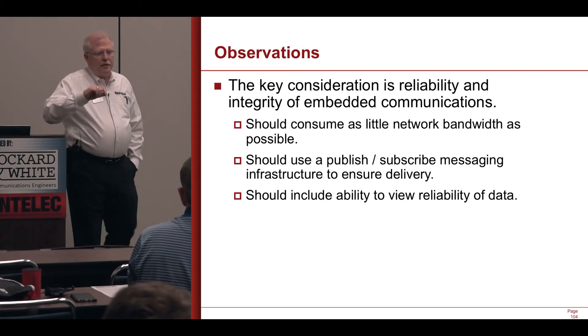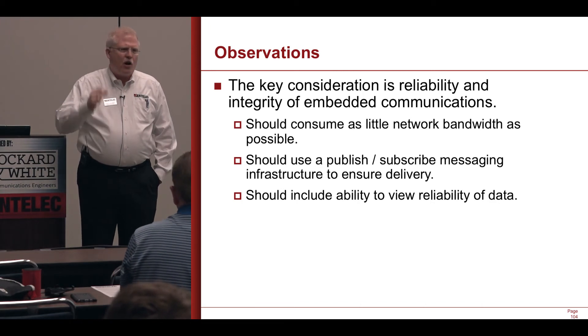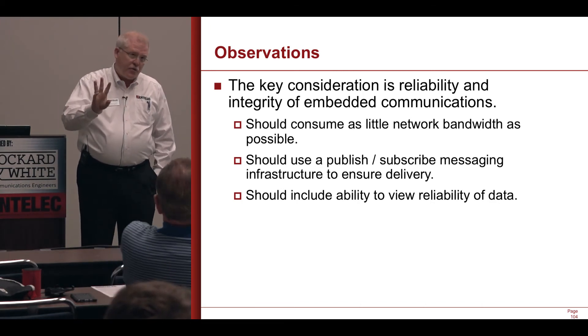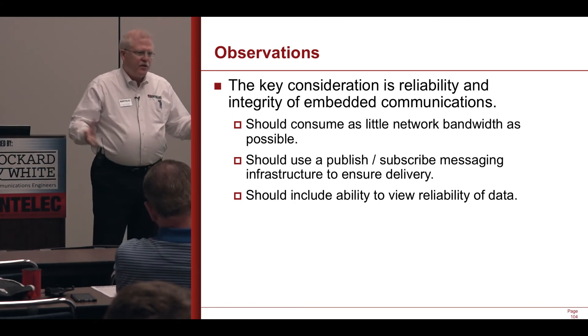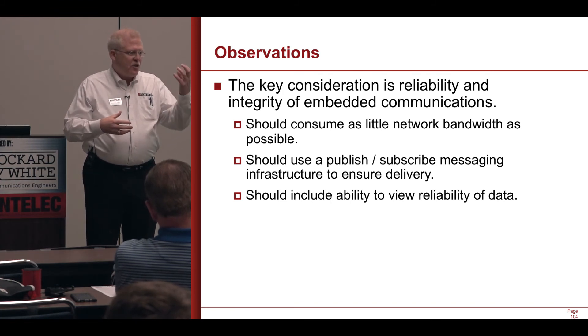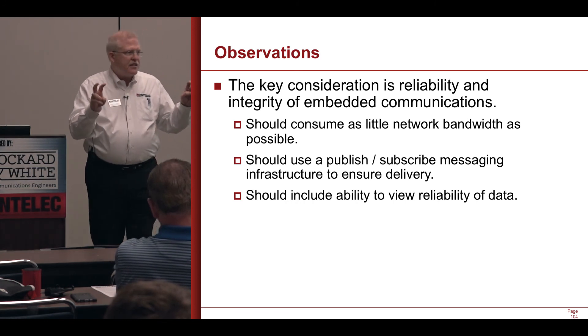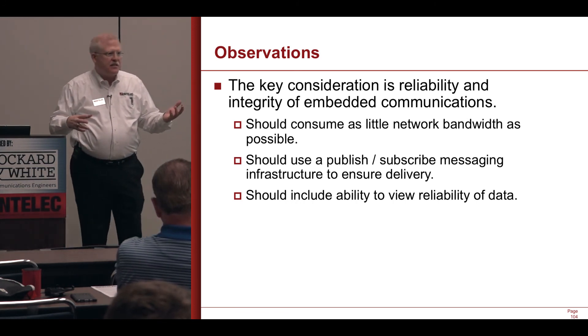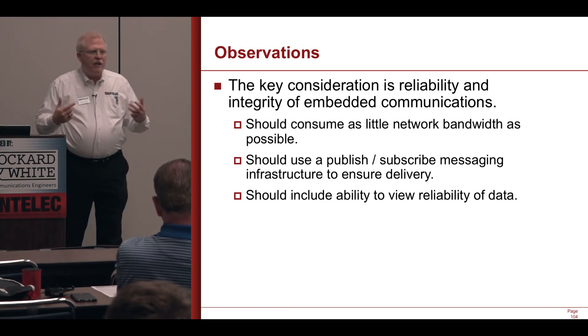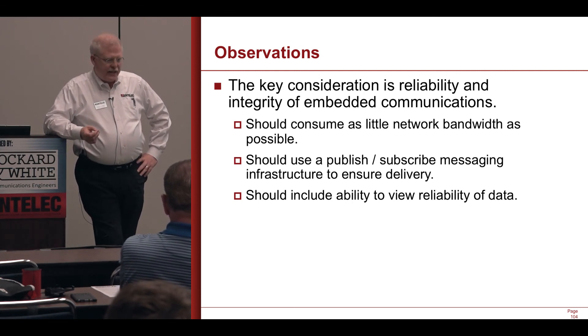The key thing about SCADA: if you want a high-performance, high-reliability SCADA implementation, it's all about communications. There are three parts to that: field data communications, network communications, and internal application communications. The polling engine has to ask for the data, it gets sent to the real-time database, then it goes from the real-time database to the historian. If there's redundancy built in, it has to go to all the other places that need it. If you're evaluating a SCADA technology, pay particular attention to that, because if you have a problem with a SCADA product, it's going to be because of its internal messaging.